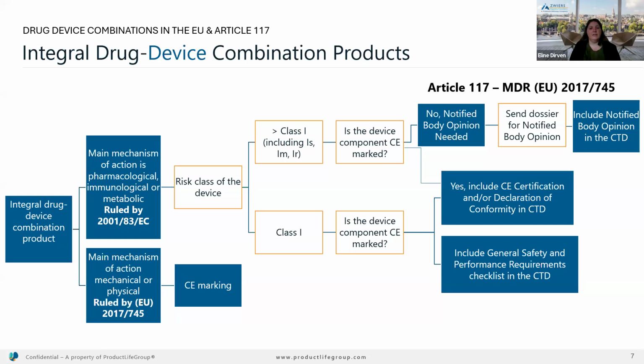In case the classification is higher than class 1, which includes that it's in sterile condition, with a measuring function, or as a reusable surgical instrument, however probably that last one will not fit with an integral drug device combination product, then notified body involvement is needed. It could be that this has been done already, which means it should already contain a CE marking. But you should also keep in mind that you have to use it as intended, so don't deviate from that. If that is the case, then you can just include the already available CE certification and the declaration of conformity in the CTD, which you can ask from the legal manufacturer which assigned that CE marking.